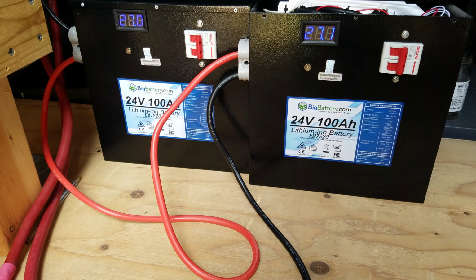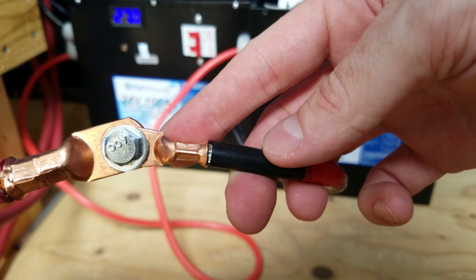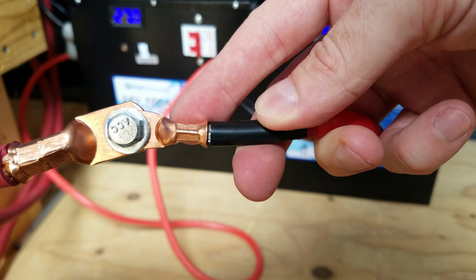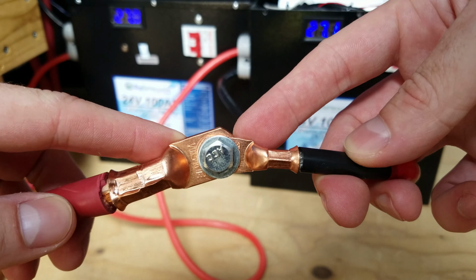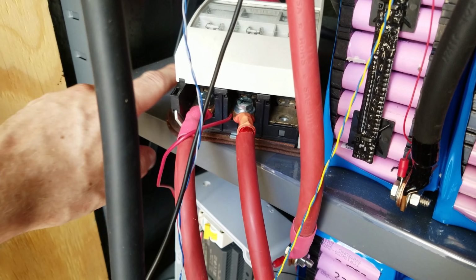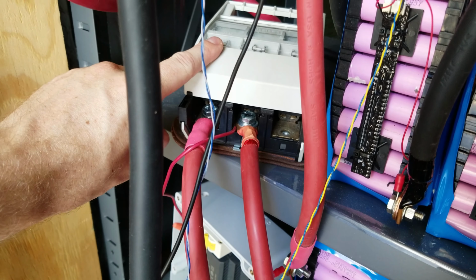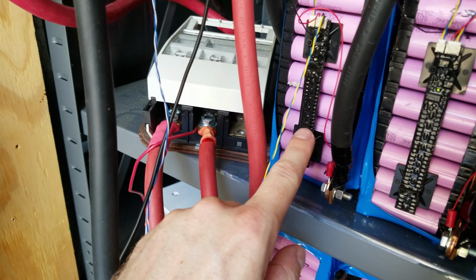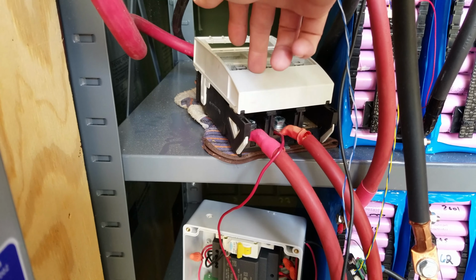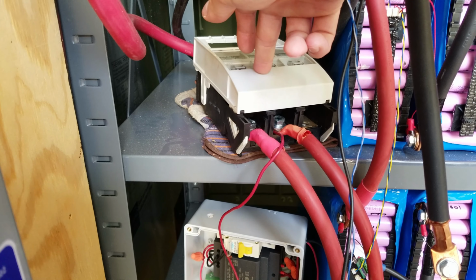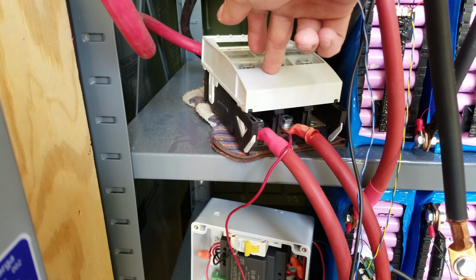Alright, so I got these batteries out in the battery shed here. I just crimped a copper lug onto the silicone cable and attached it to my original bolt, and that goes up into this fuse disconnect. I've disconnected all of my other lithium batteries, and there's a 125 amp fuse in this fuse disconnect box as well for added safety.